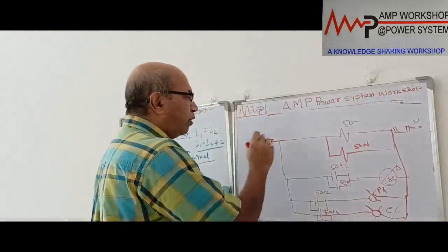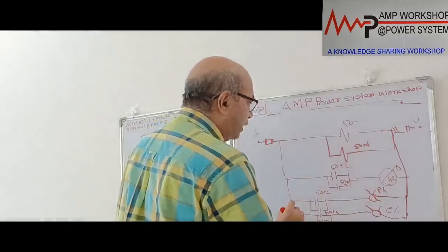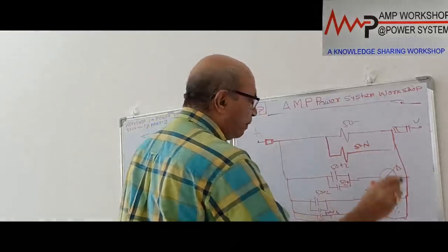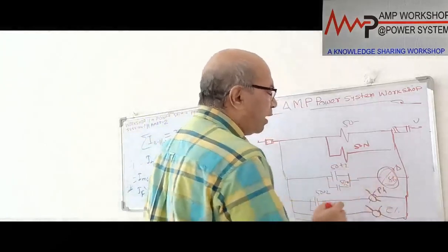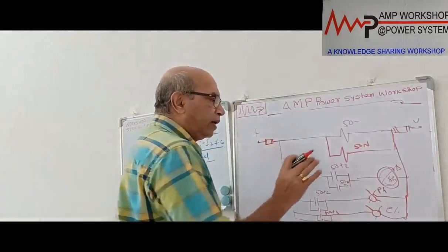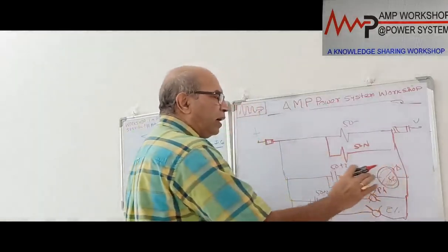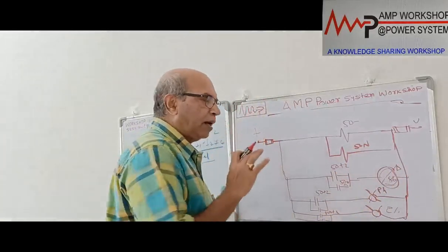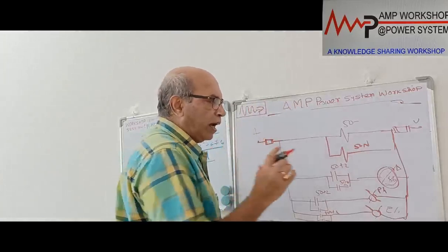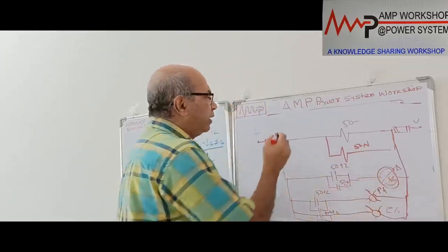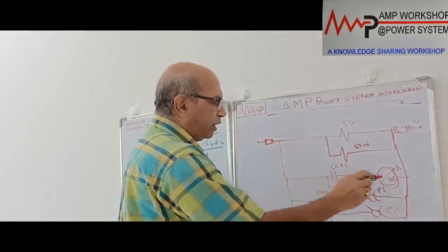If we want to continue the bus wire, we can put another indication lamp at the end for the bus wire indication. This way the 86 lockout relay with hand reset is required. Until you reset the relay, you cannot close any of the incomers, bus coupler and outgoing feeders. This relay has multiple heavy duty contacts that will be connected in the trip coil of the breaker.